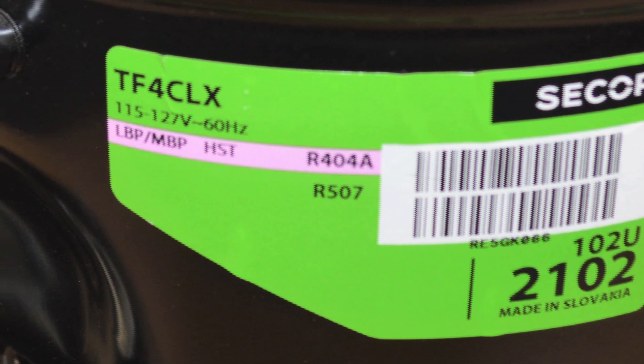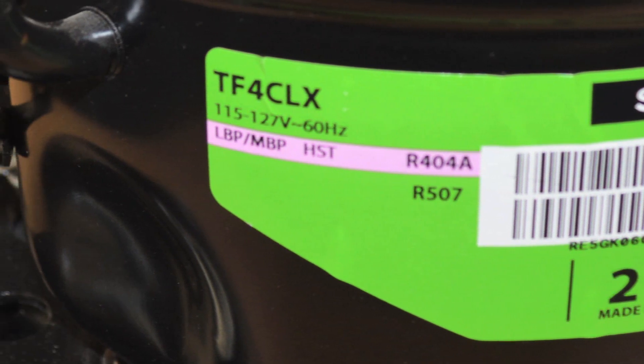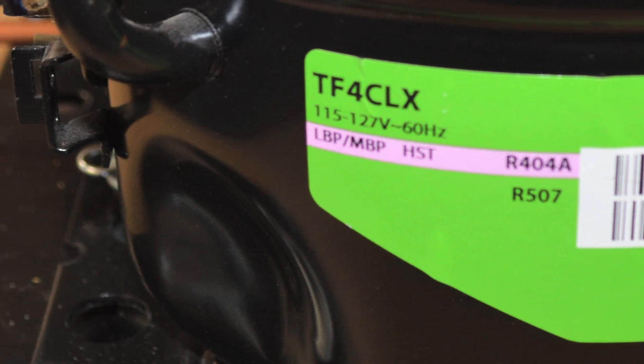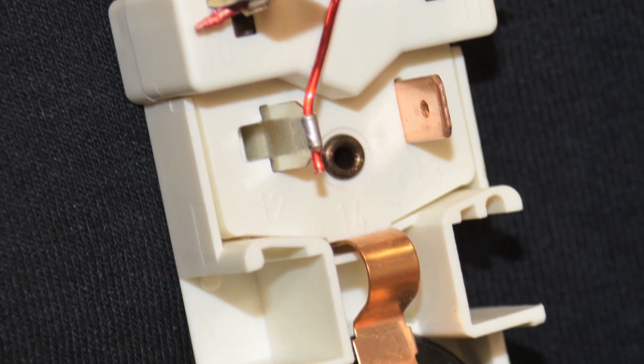The specific model we'll be using for our demonstration is a Danfoss TF4 CLX compressor, which uses a current relay to energize the start winding.